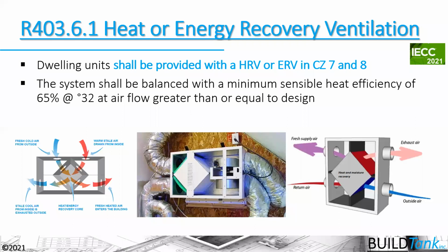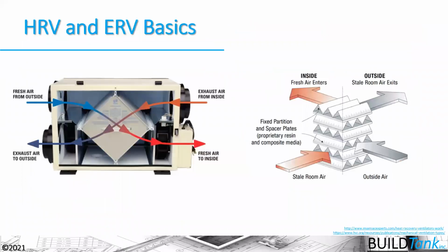So how does a balanced ventilation strategy work? The basics is that you have an airstream coming from the outside to the inside, and an airstream coming from the inside to the outside, and their flow rate, their CFM rate, is equal to each other. These airstreams are passing through a core. That's this kind of diamond-shaped device here, but those airstreams don't touch each other.